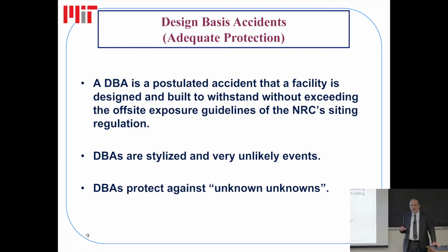Still, the large break LOCA is a major design basis accident. There have been some efforts to relax the requirements, because it's not just the accident itself, it affects many other things. For example, in the containment, there is the containment spray system that sprays water into the containment if there is a release of radioactivity.